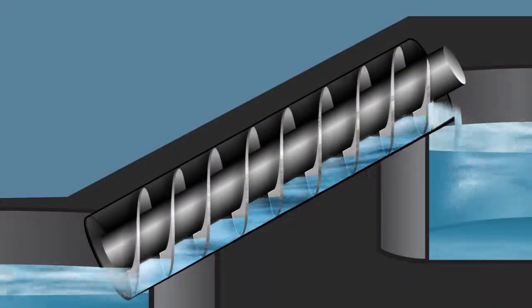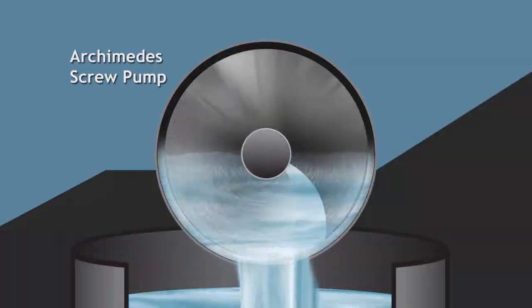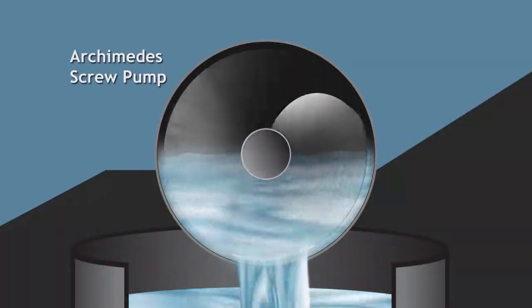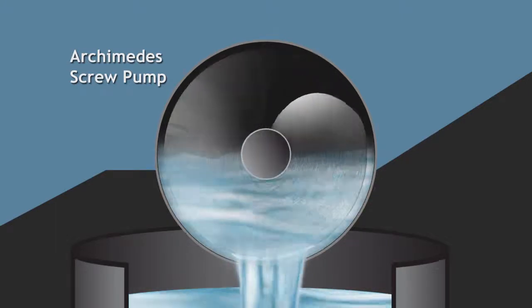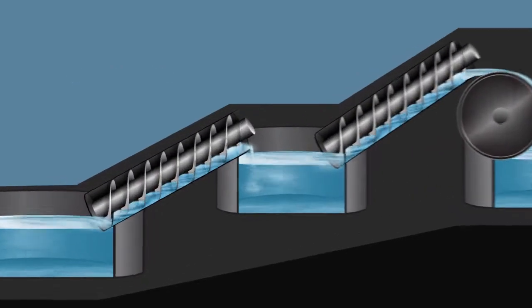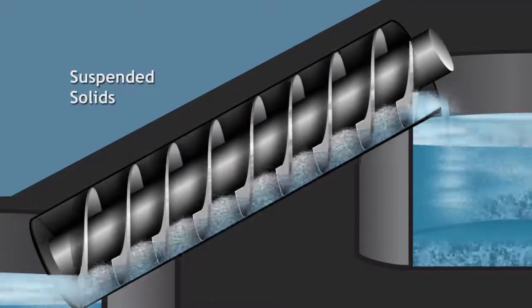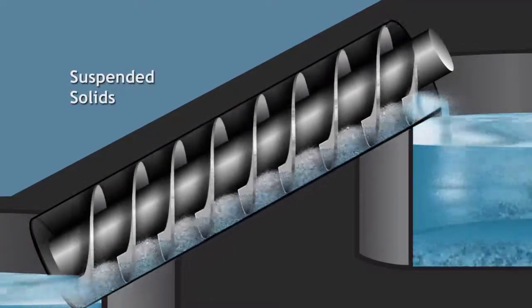This is the beginning of the wastewater treatment plant called the Headworks. This is where we use two Archimedes screws to pump all of the solids and liquids up to the screens. An Archimedes screw is a simple and effective way to move water uphill. Also called a screw pump, the Langley version uses a helical screw turning within a tube to lift wastewater up to the drum screens at the start of the treatment process. Archimedes screws are often used in wastewater treatment plants because they can pump water with suspended debris and solids without clogging the system.